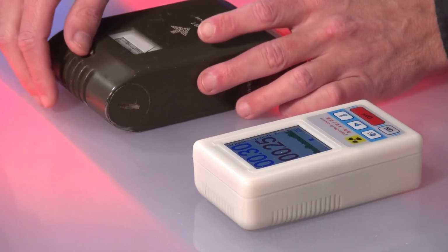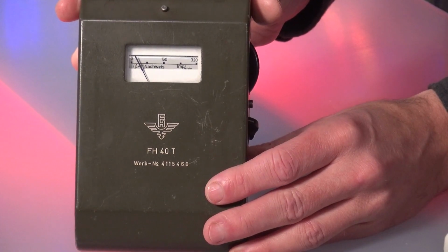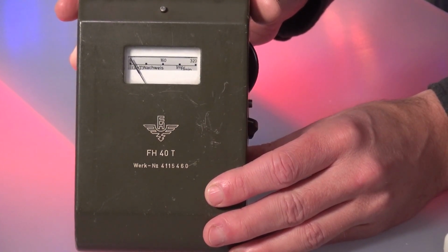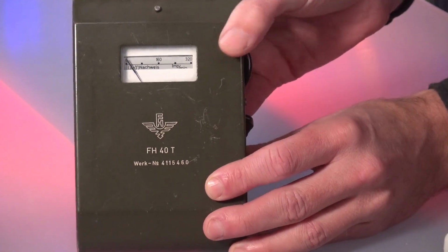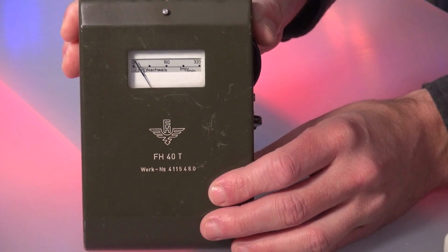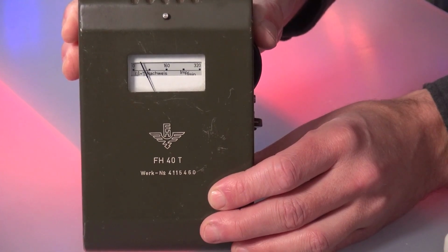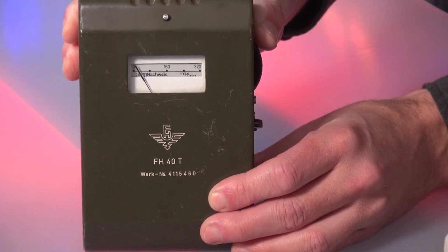The pitfall is that we have no sensory perception of this type of radiation. We don't feel it. And what we don't feel must be detected by other means. And for this, we need test equipment that can do this. These measuring devices, which are among the oldest measuring instruments that we have for this, include this device that was used by the German armed forces, for example, and also in civil defense, the FH-40T. And as you can see, if we look at the display here and wait a bit, then due to the natural radioactivity that surrounds us all, as I said earlier, this device deflects from time to time, as you can see up here in the display.